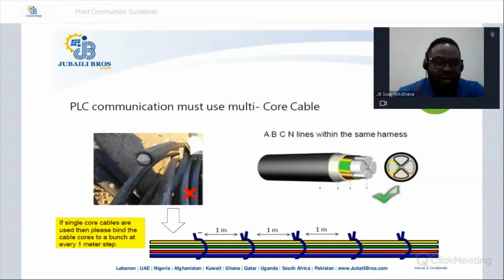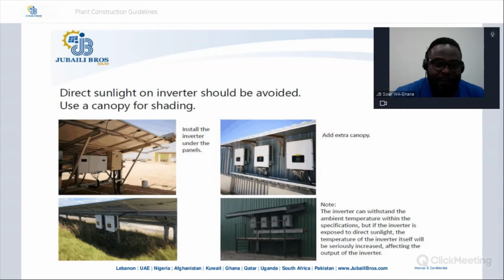distribution board or the LV panel, whatever. So bundling it at every 1 meter is just like having a multi-core cable. So the best is, if you can afford it, you go for a multi-core cable, as against single core cables that have to be banded like this. That is if the communication that you are choosing is PLC. Okay, this is the minimum advice from Huawei.